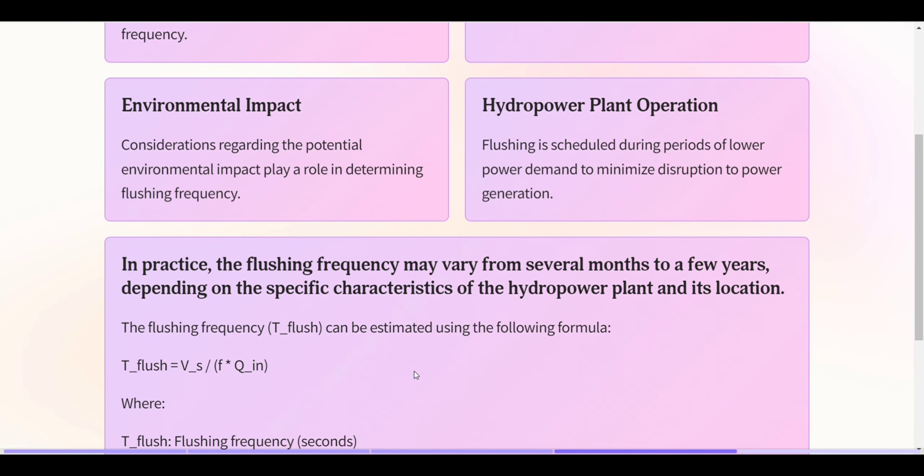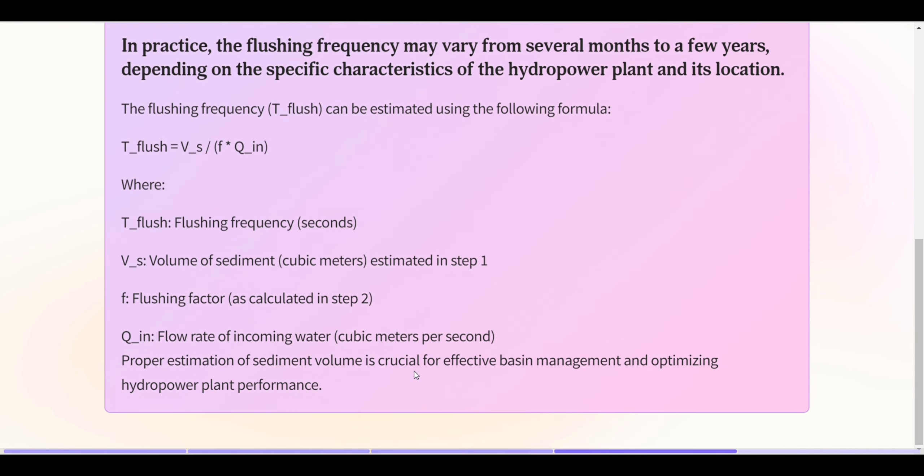In practice, the flushing frequency may vary from several months to a few years, depending on the specific characteristics of the hydropower plant and its location. The flushing frequency can be estimated using the following formula, where T_flush is flushing frequency, V_S is volume of sediment estimated in Step 1, F is flushing factor, and Q_in is flow rate of incoming water.